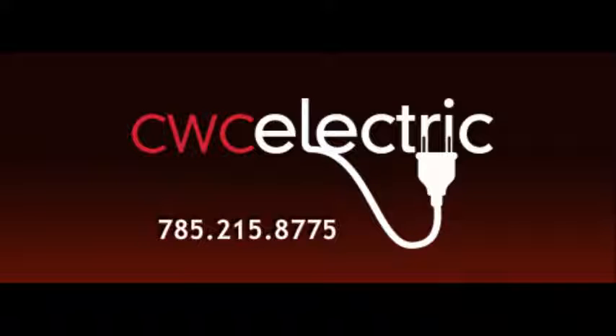Simple thing that's really a big danger sign is if you see flickering light, if you have an appliance or lights that are flickering, that indicates there's a loose connection somewhere. A loose connection is arcing. Arcing is a very high temperature. It's thousands of degrees, and it's sitting there. It's burning an outlet. It's burning a wire nut. It's burning something somewhere when you see that flickering. And so that has to be found. It's a huge fire hazard. It's a huge sign. Your house is trying to tell you something. There's something wrong. Get it fixed.